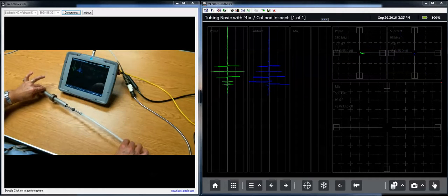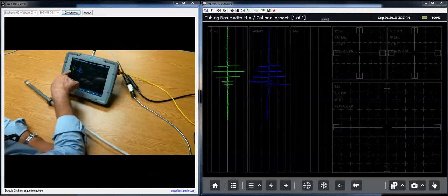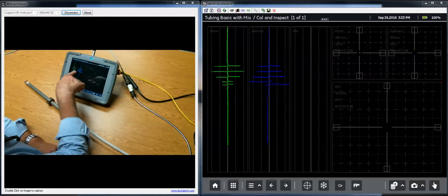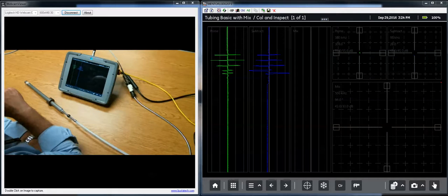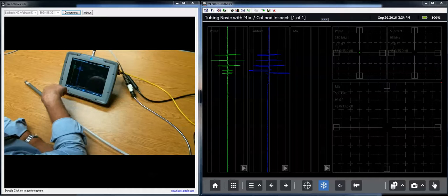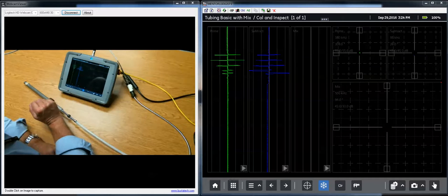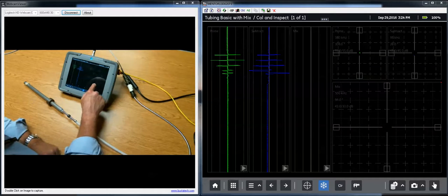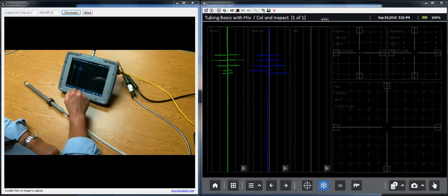And what we got there, I'll let that run for a second. The green is our primary frequency, a higher frequency, in this case 380 kilohertz. The blue trace is our subtract frequency, the lower frequency. I'm going to freeze that. That's the lower frequency that I want to penetrate well and see the plate. And there's a magenta, or hot purple color, that will show us the result of the mix. We haven't calibrated yet, so the mix is way off screen at this point.